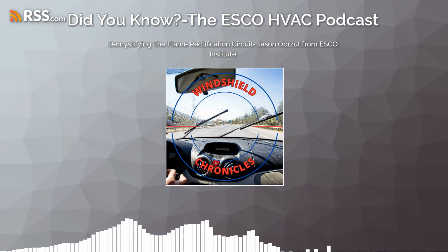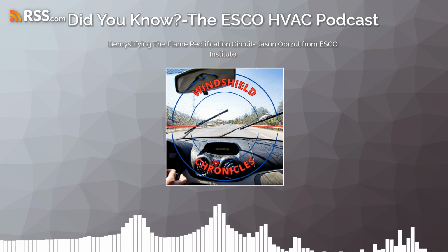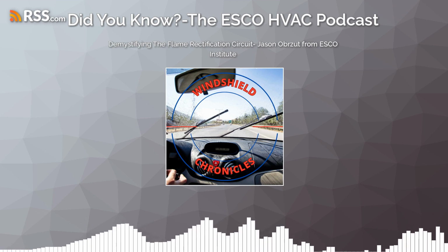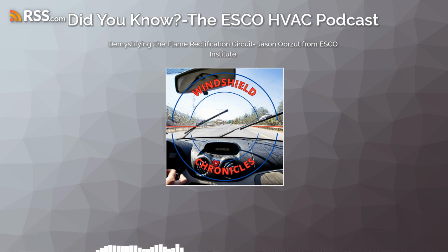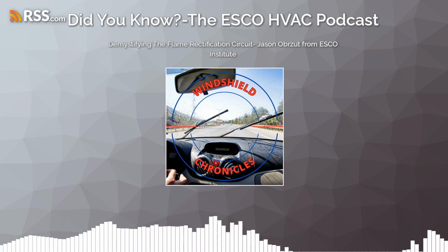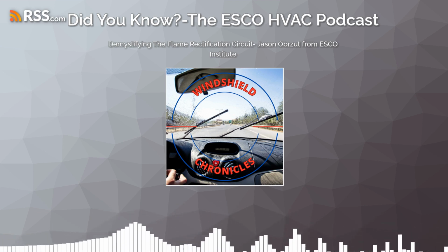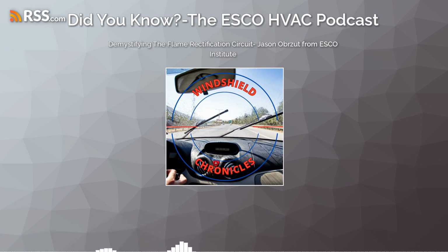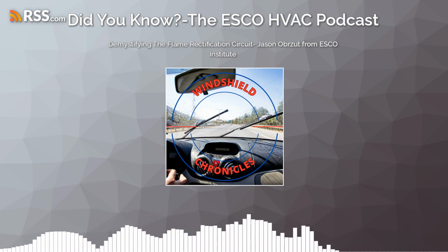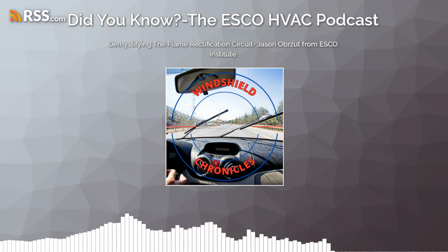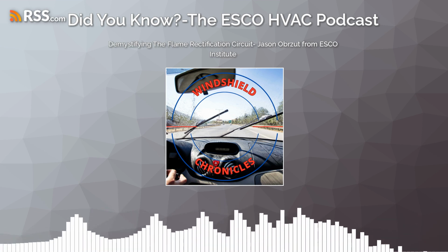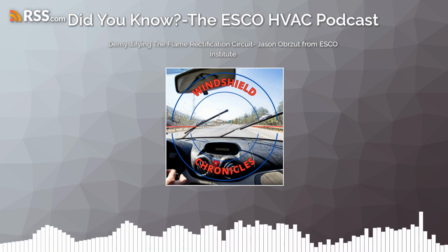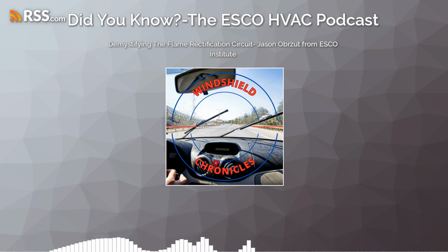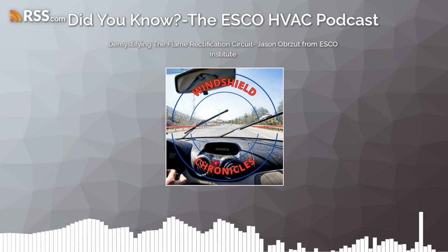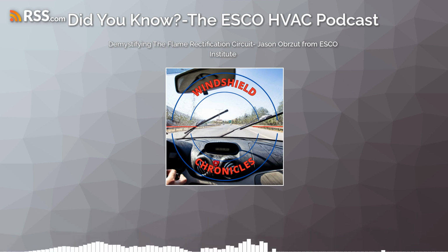So in a classroom, here's the way that we want to show that. Or even if you're a technician and you want to verify it yourself, next time you're sitting in front of a gas furnace, here's what you do. So let's walk over to a meter. Let's put our meter on volts AC. My thermostat is not calling for heat, but I have power applied to my furnace, which means everything on my high side has the potential for voltage right now. So if I go from ground directly over to my flame rod, I am actually producing right now 43.4 volts AC directly onto my sensor, my rod.